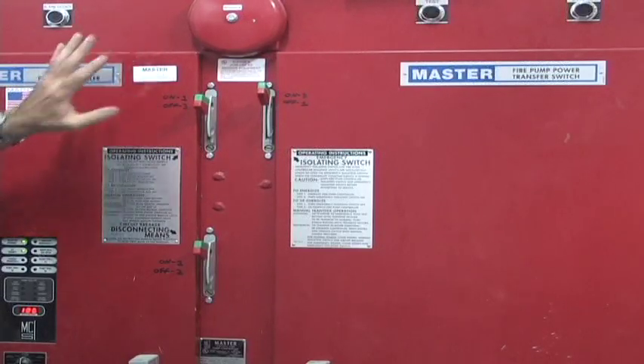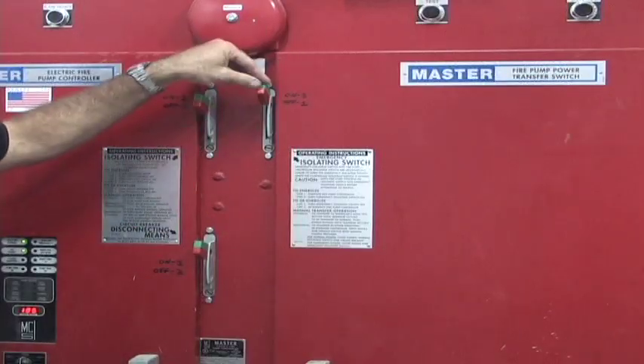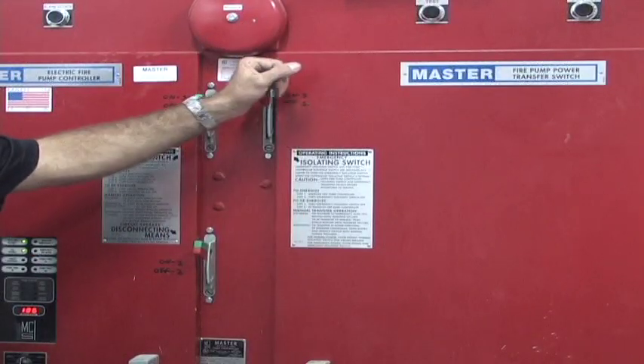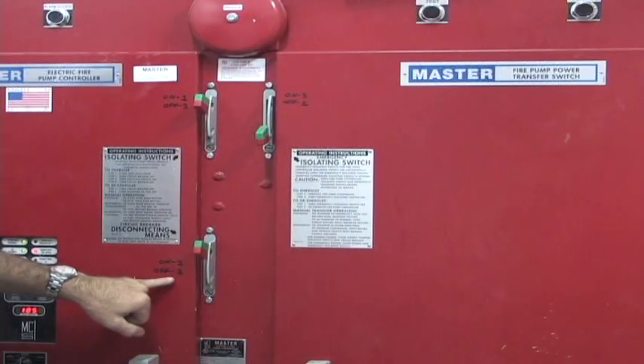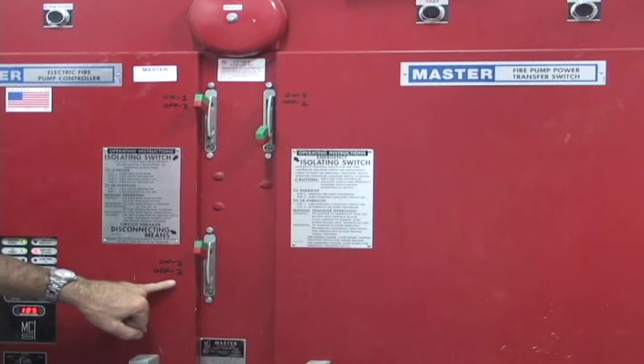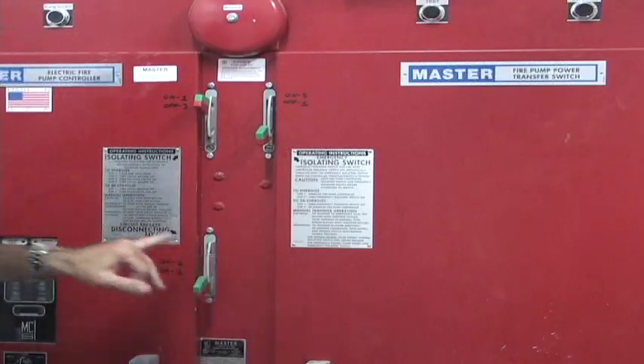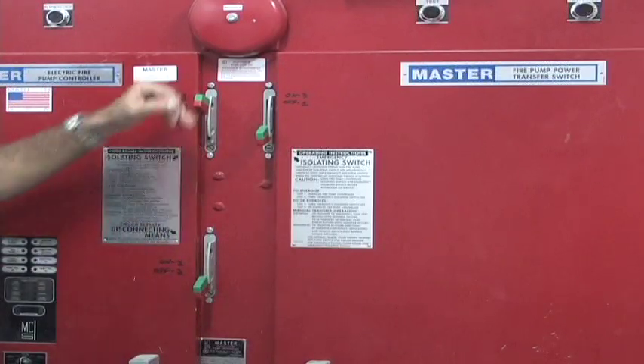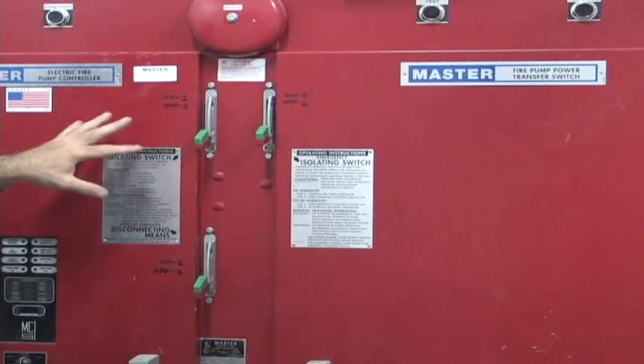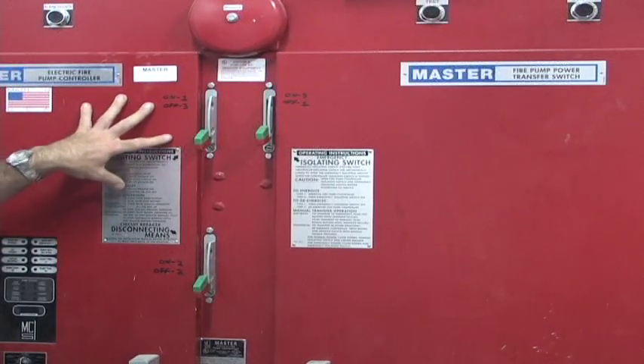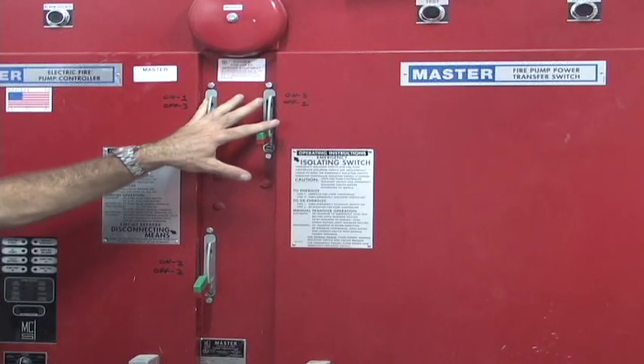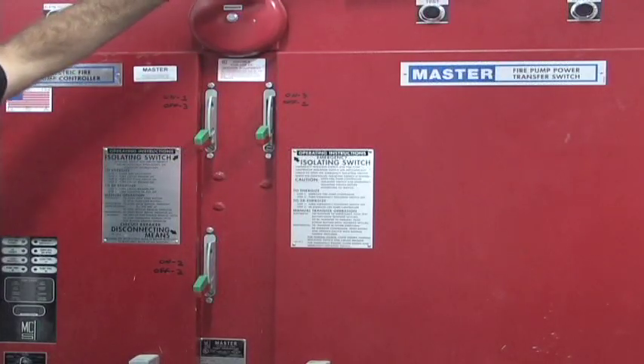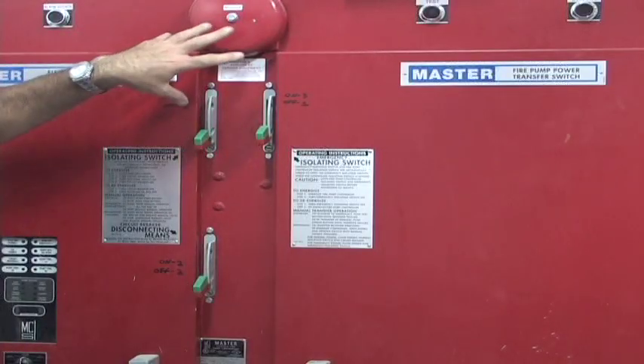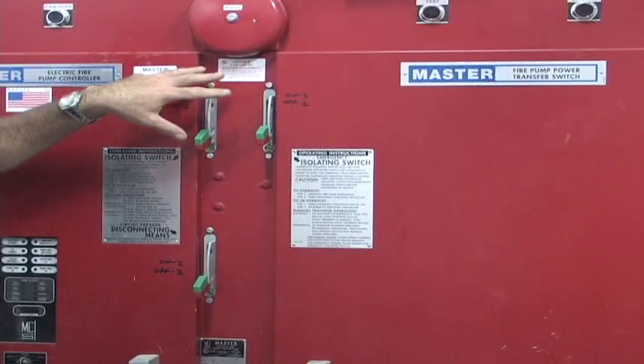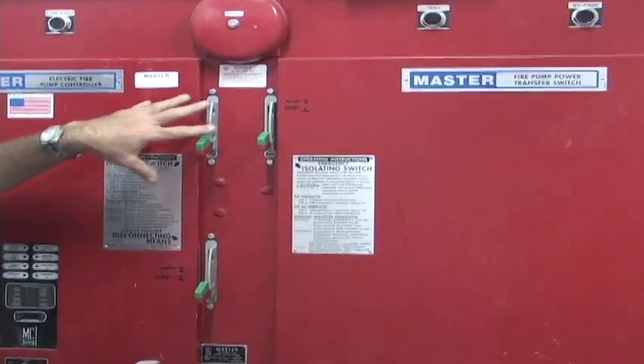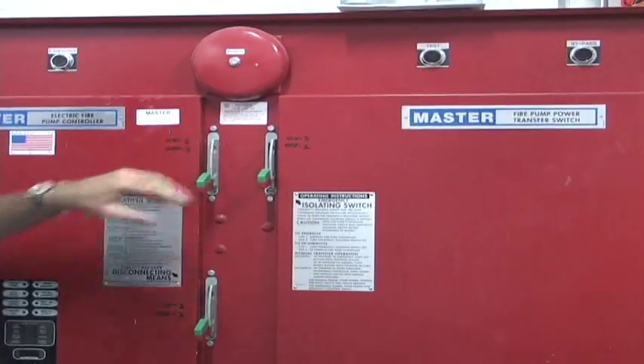If we were to shut this fire pump off, we're going to start with emergency first, where it says off number 1. We'd come over to the circuit breaker disconnecting means, we'd shut this one off. Then we'd come up to our 3rd one, the isolating switch, and shut this off. Now our fire pump is completely shut off. When we have a loss of power to this fire pump, we have a relay that shows that we have power loss, which goes back to the fire alarm panel and gives us a trouble or a supervisory saying that the fire pump has lost power. You need to go check it all out, the switches.